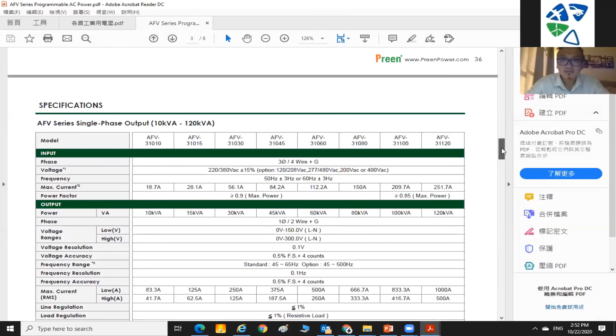For the AFV series, and for most power supply manufacturers, if you want to overcome that inrush current, you need to plan ahead. For example, if your inrush is up to 100 amp, you need to choose something like a 30 kVA unit. But with ours, you can tell us how long your inrush lasts and how much current it will require, and sometimes we can choose a lower kVA unit but enlarge the IGBT to help you overcome the inrush at the beginning.